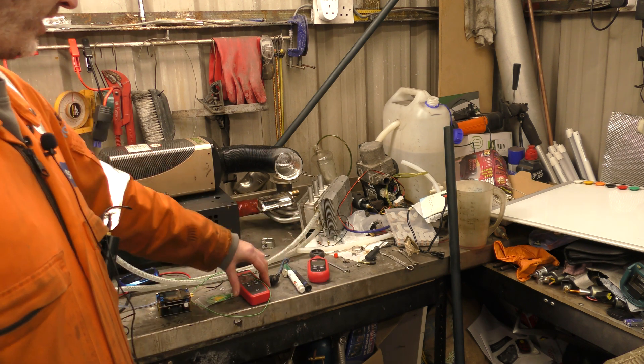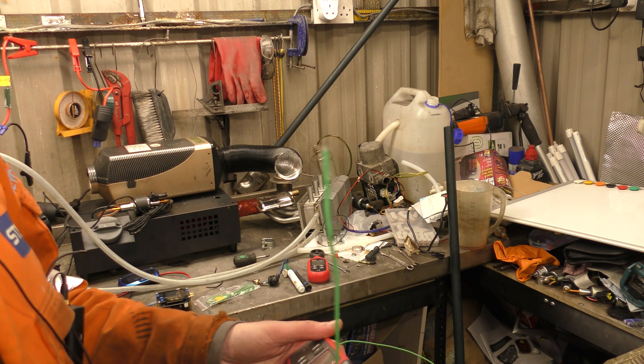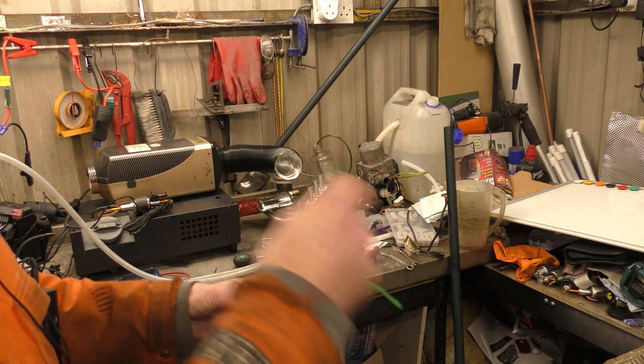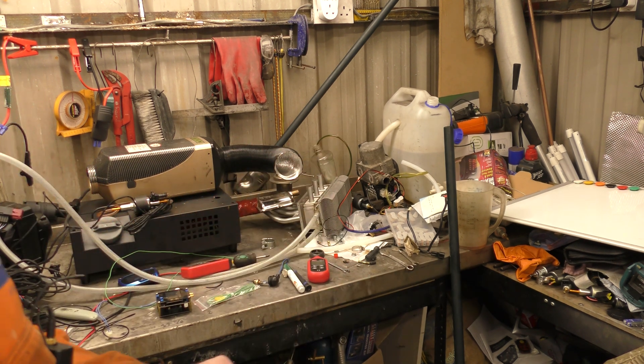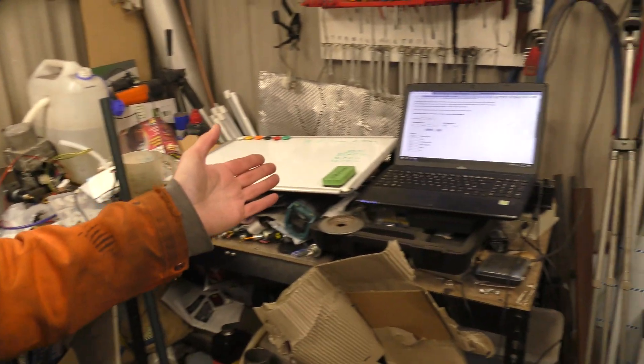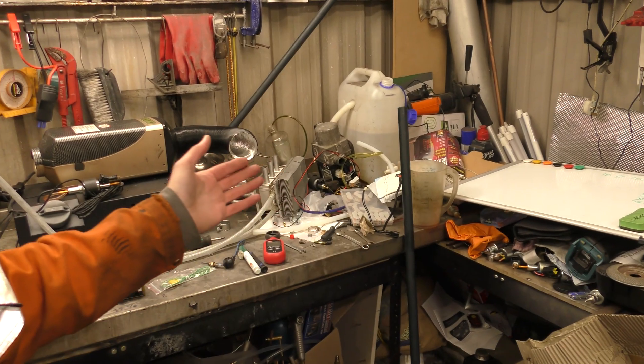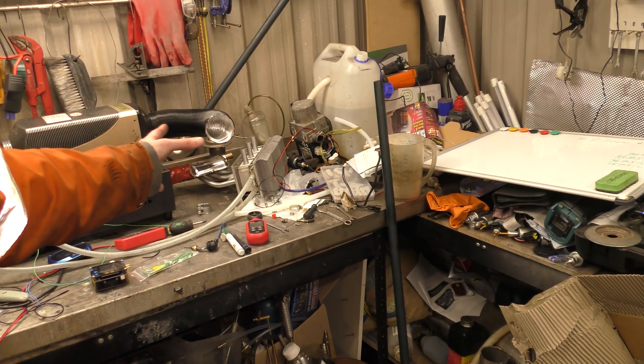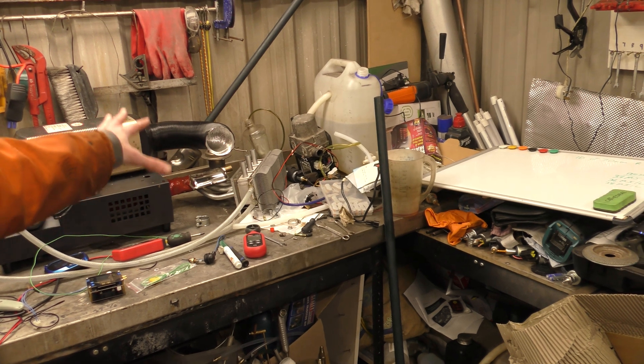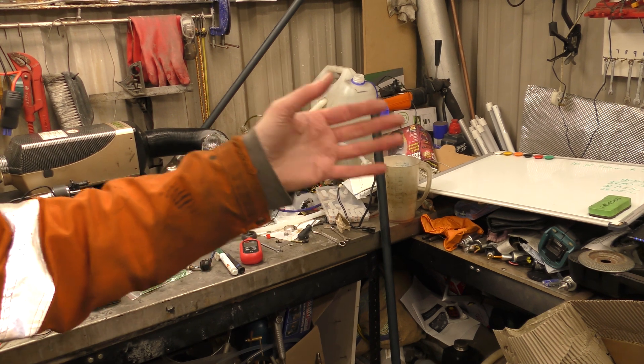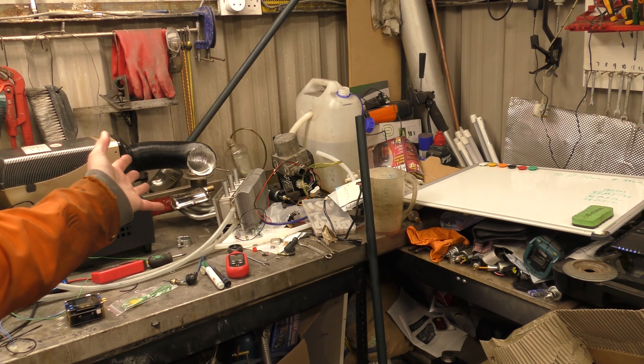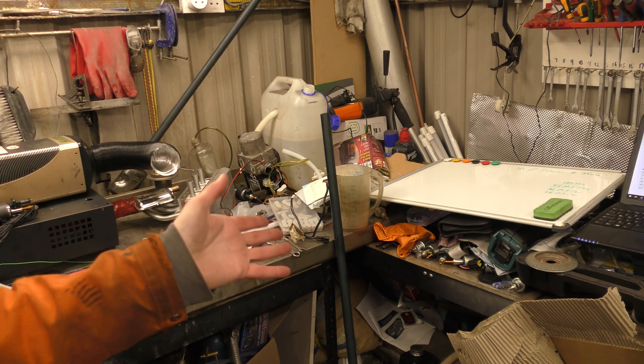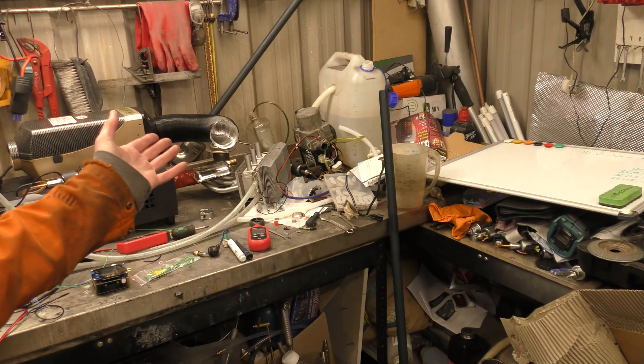We've got an anemometer and a thermometer for measuring the temperature of air going in and coming out. We have a change of temperature and then using mathematics as well as lots of online calculators on the laptop, we're going to work out how much air comes out of this heater in volume and then the change in temperature will let us know how many kilowatts of heat is being imparted into the air. Then we'll see if that roughly works out with how much diesel that it is burning.